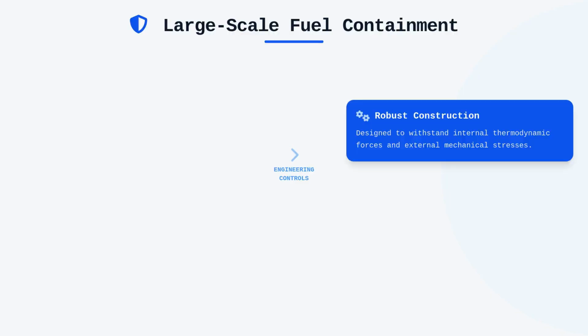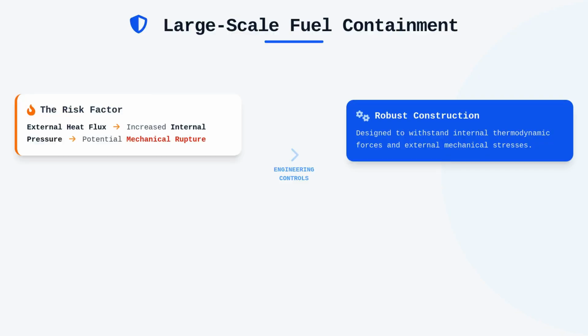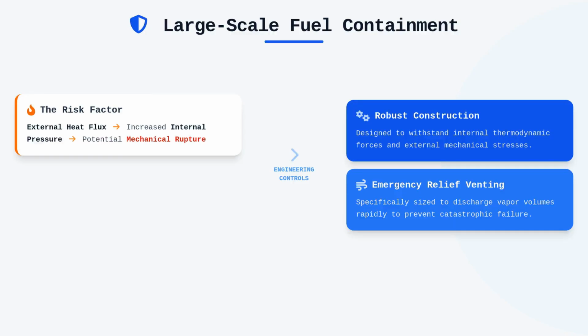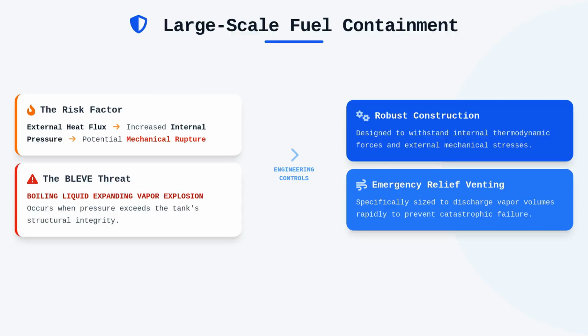Large-scale containment of massive fuel loads requires an entirely different set of engineering controls, specifically concerning tank construction and emergency relief venting. Tanks containing flammable liquids are pressurized vessels that must withstand both internal thermodynamic forces and external mechanical stresses. If a fire starts in the facility, the resulting heat will increase the pressure inside the tank, which could lead to a mechanical rupture if the vent cannot discharge the volume of vapor produced by the fire's heat flux. Emergency relief vents are sized specifically to handle this rapid rate of expansion, acting as a safeguard to prevent a boiling liquid expanding vapor explosion, or BLEVE.